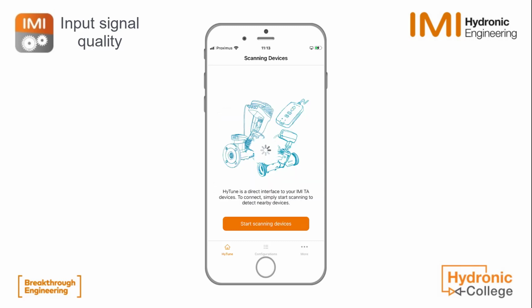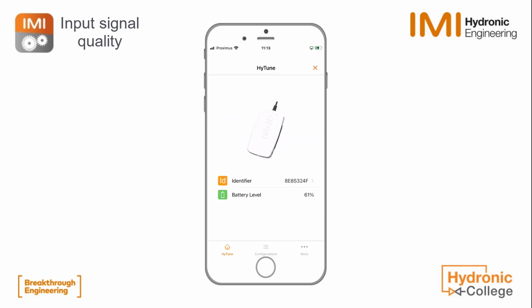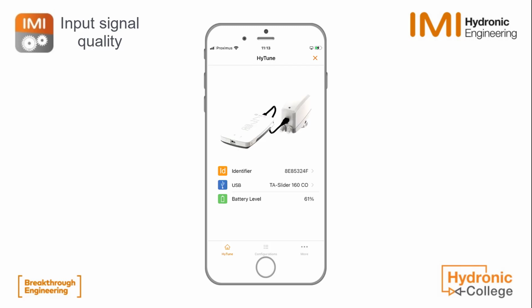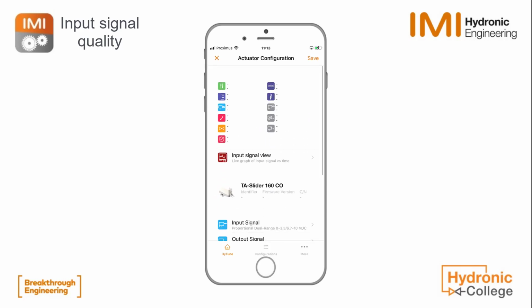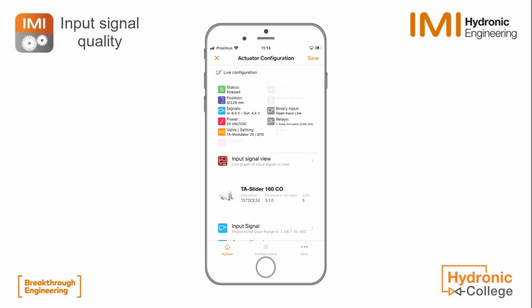So here we are connecting to a TA-Slider, in this case a slider 160 change over, via HyTune and the dongle. And if we open the screen, then we see already quite fast in the signals line that there is some fluctuation. We also see the output signal is fluctuating between 4.7 and 6 volts. So we click on input signal view.